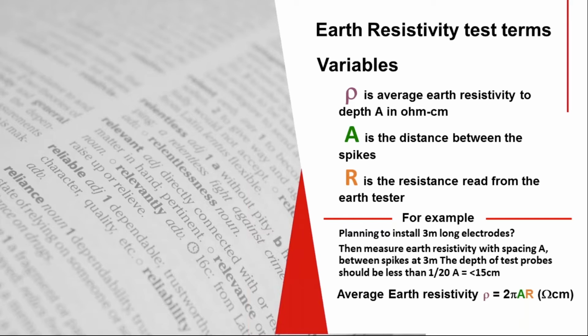So you take your R, which is your reading off the display on the tester, and A, your spacing, and plug that into the formula. That gives you your resistivity to a depth equivalent to A, in ohm centimeters.